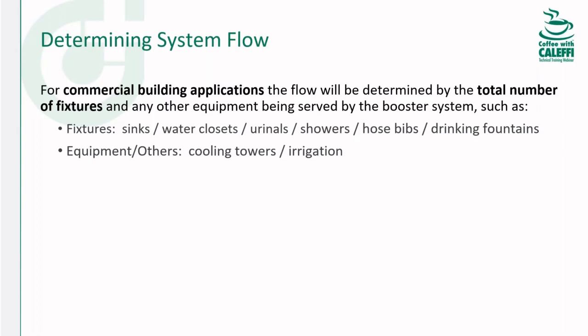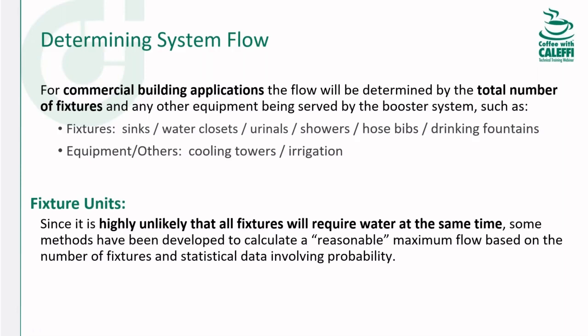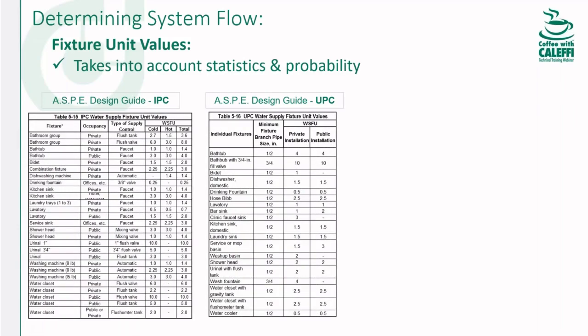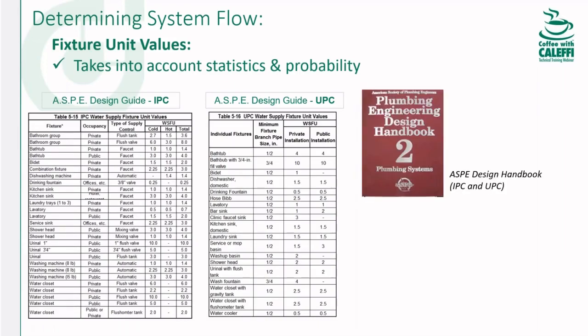What you're going to do is look at studies that look at probability and things like that. So you are going to add up all the fixtures, but what you're going to come up with is what they call a fixture unit value. There are some sources out there for this, but you'll end up looking at a table, and again, it takes into account statistics and probability. A couple sources: the Plumbing Engineering Handbook. Everybody that's a member of ASPE, the American Society of Plumbing Engineers, is familiar with these books. Volume 2 is a design handbook that has fixture unit procedures in there, and tables and graphs.